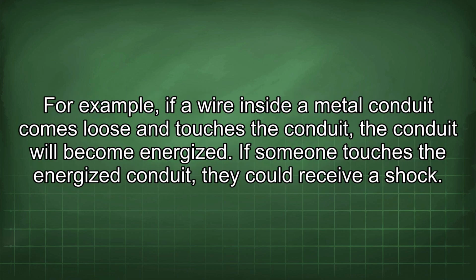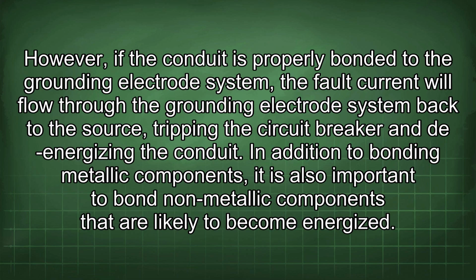For example, if a wire inside a metal conduit comes loose and touches the conduit, the conduit will become energized. If someone touches the energized conduit, they could receive a shock. However, if the conduit is properly bonded to the grounding electrode system, the fault current will flow through the grounding electrode system back to the source, tripping the circuit breaker and de-energizing the conduit.